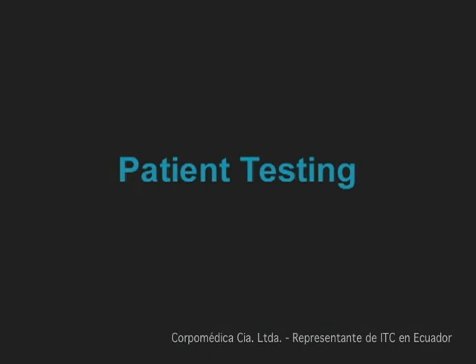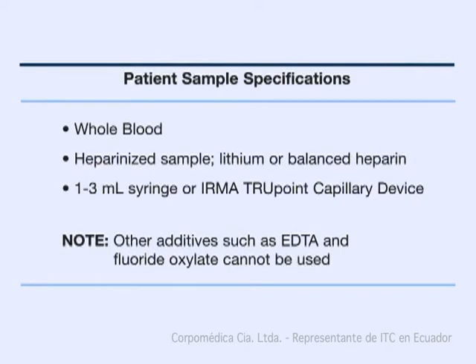When testing patient samples, use fresh whole blood collected in either a heparinized 3 mL or smaller syringe or the ITC capillary collection device. The minimum sample volume requirement is 200 microliters when collecting in a syringe and 125 microliters when using the ITC TruPoint capillary device. Please note that the use of sodium heparin may alter electrolyte values. EDTA or fluoride oxalate cannot be used.